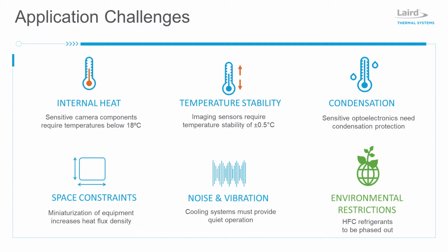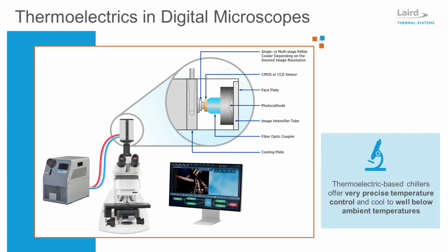In addition, government environmental regulations are motivating laboratories to replace traditional hydrofluorocarbon (HFC) refrigerants with more environmentally friendly options that have low global warming potential. Thermoelectric-based chillers provide zero global warming potential. With the ability to cool well below ambient temperatures, recirculating thermoelectric chillers are a better option than passive solutions, such as heat sinks and fans or ambient liquid cooling systems. Their plug-and-play design provides quick and easy installation in any laboratory environment.